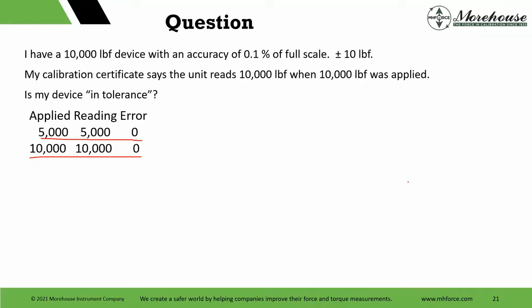Looking at this graph here, this basically says if I change the question and say, hey, I sent this to a lab for calibration, and they reported 0 error, yet when I graphed it, because of their uncertainties and because of the contributors that go into the TUR, when I graph this and everything's reading perfect, I have 12.39% risk, meaning these areas of the curves over these lines are a risk.